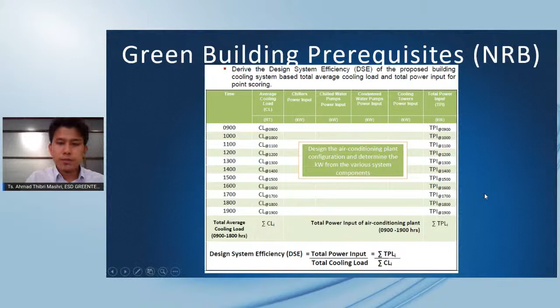Of course, if there is no such guideline, some chiller manufacturers or operators can claim that their chiller system is efficient, but at what condition? Perhaps it's only efficient at 80% load or 100% load, but in actual building conditions that may not be the case. So green building facilitators like us need to ensure that the design takes care of the low load condition, and we need to show that the system configuration is able to meet the kilowatt per ton requirement at the weighted average and generally at all load conditions. So this is why certification like Green RE is important, to give a structure to this.